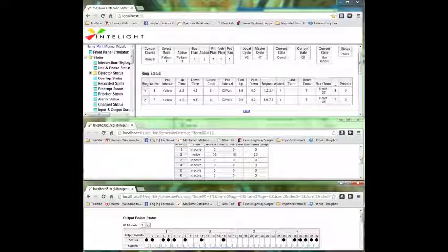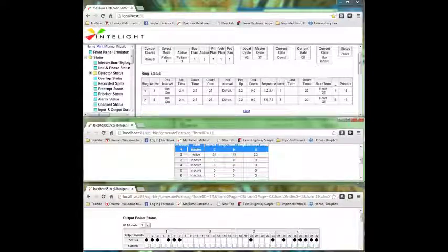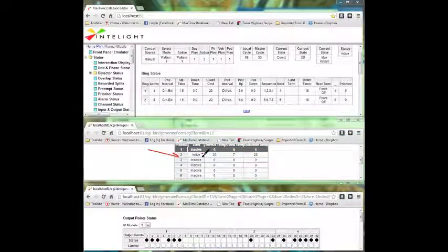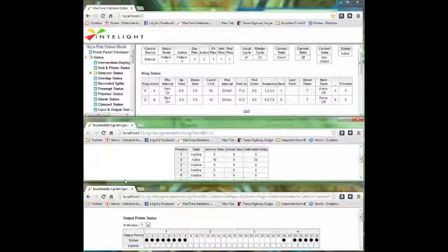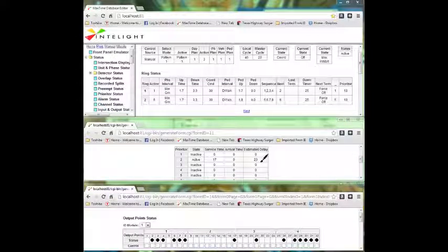Now notice that priority number 2 is now active, and I have my service time, which basically is saying that the bus is going to be at the stop bar long before I get to phase 6, because I have all the calls. So he's going to be delayed 23 seconds from his green. We can only adjust so much. We count down the service time, and it will expire when we get to phase 6.